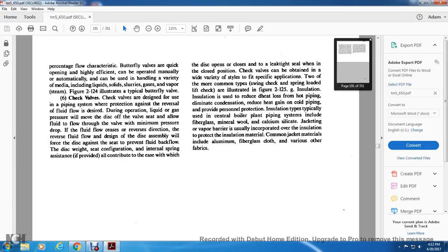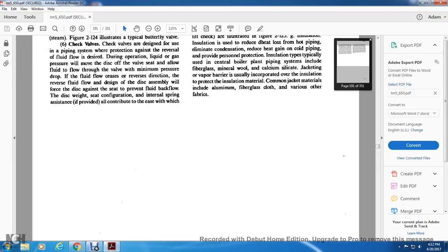Insulation. Insulation is used to reduce heat loss from hot piping, eliminate condensation, reduce heat gain in cold piping, and provide personnel protection. Insulation types typically used in central boiler piping systems include fiberglass, mineral wool, and calcium silicate. Jacketing or vapor barriers are usually incorporated over the insulation to protect the insulation material. Common jacket materials include aluminum, fiberglass, cloth, and various other fabrics.